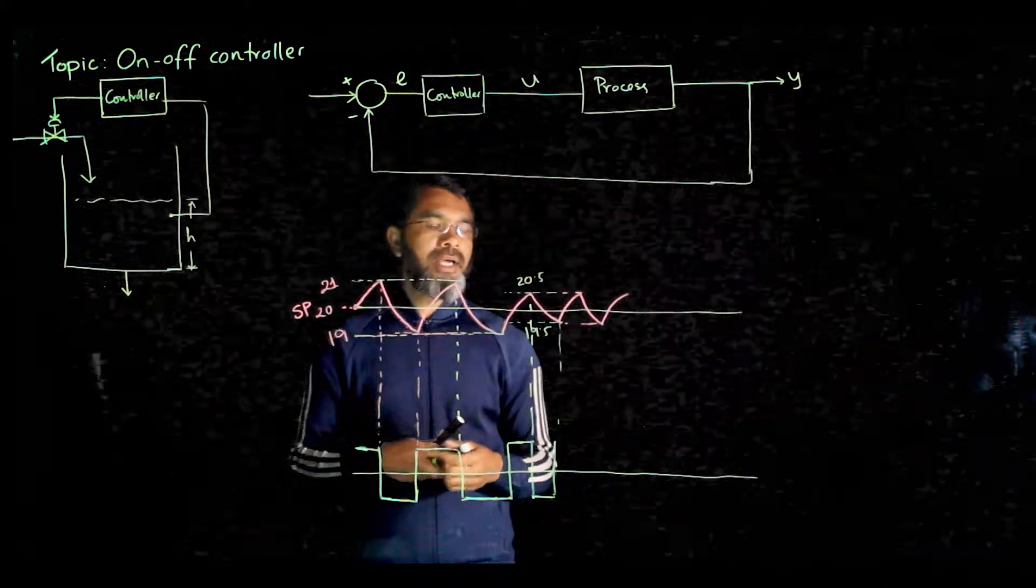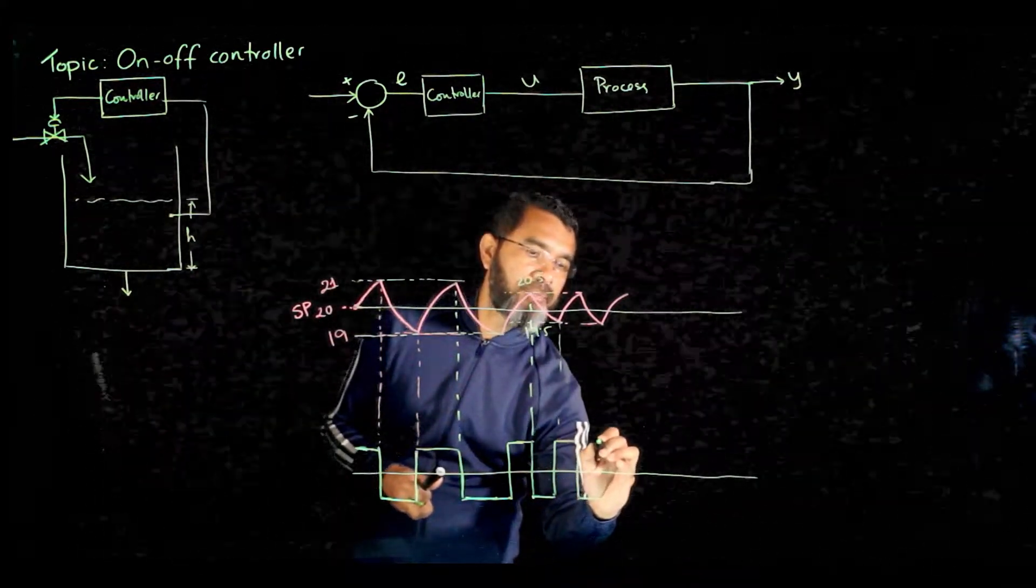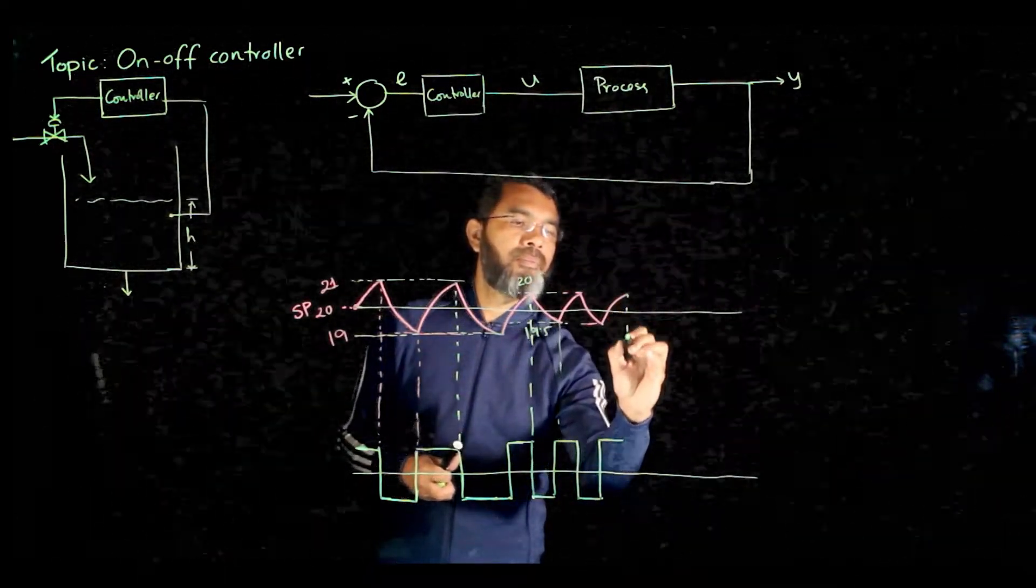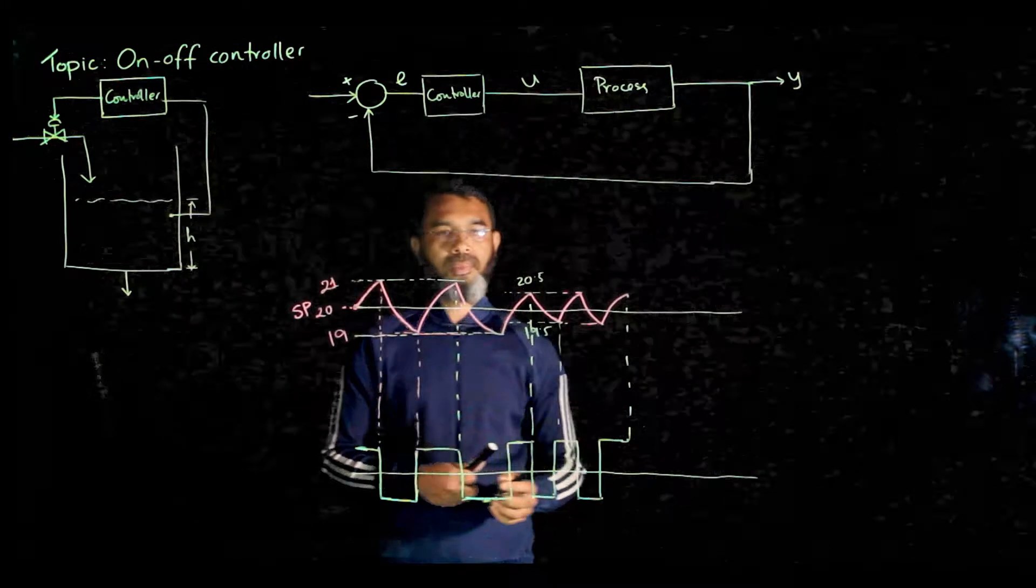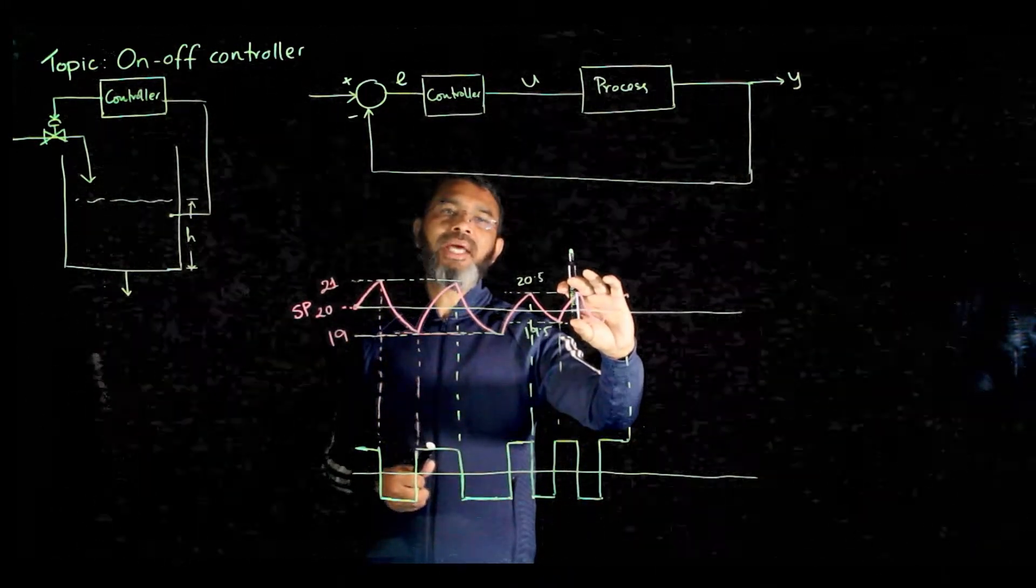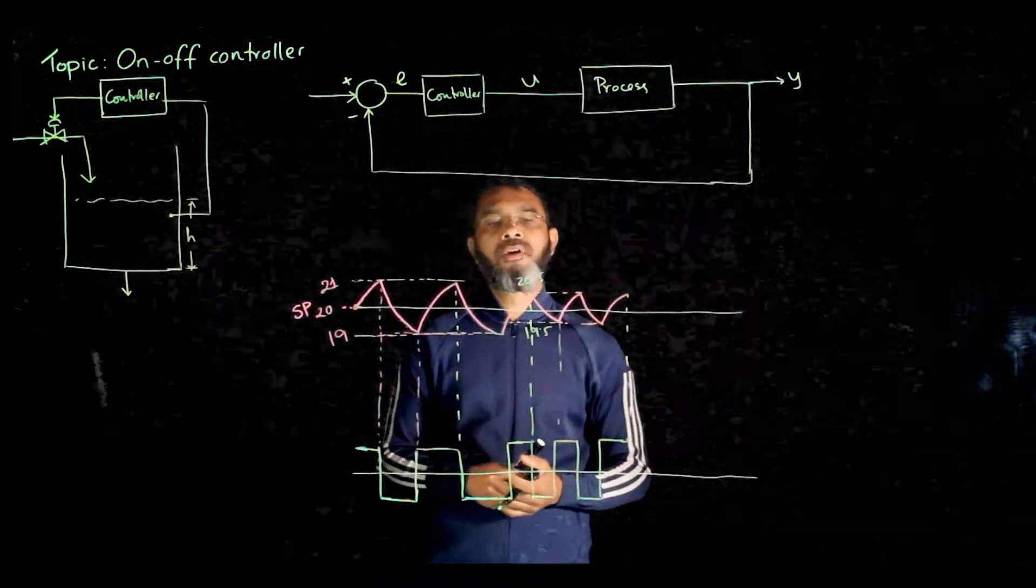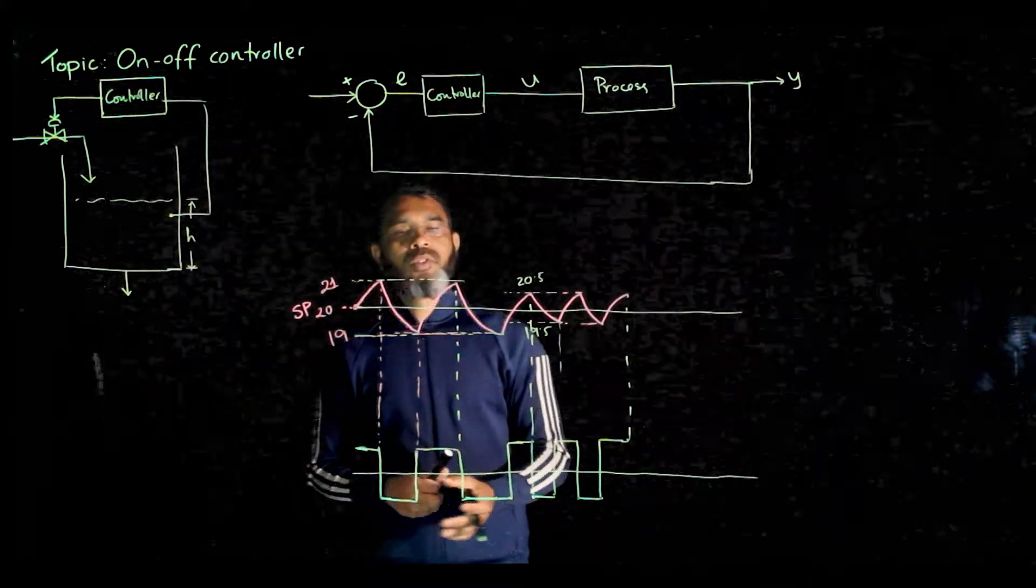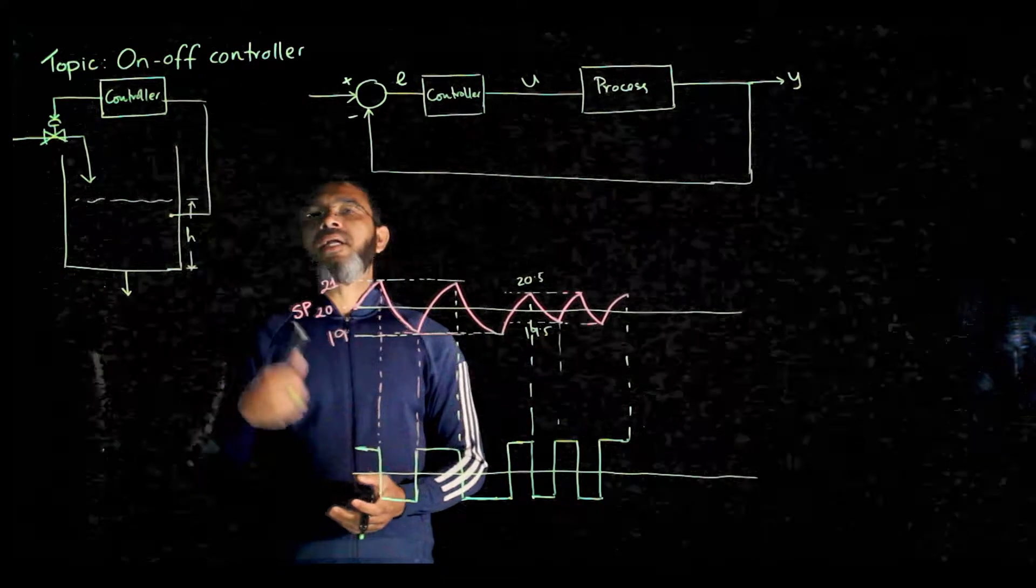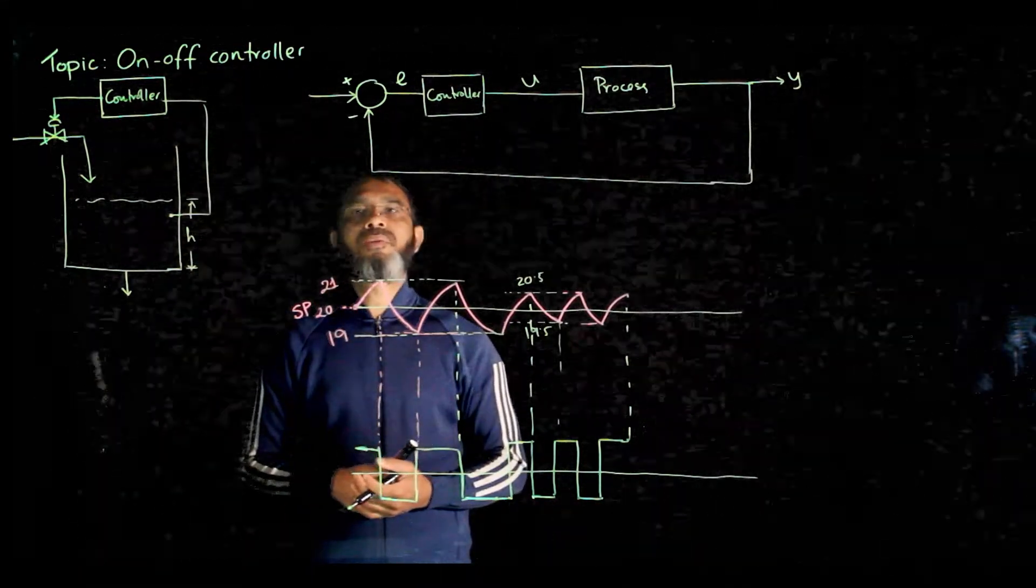But what will happen? The frequency of this valve turning on and off will be more. So if you want this level to maintain within this narrow band, the valve will turn on and off more frequently. What is the problem with that? Turning on and off the valve very frequently will cause mechanical wear and tear of the final control element.